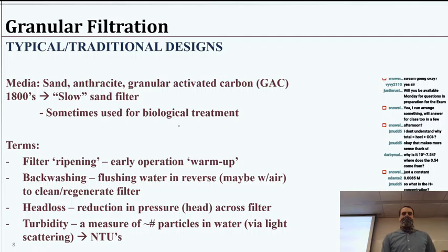The activated carbon, usually we're using that more for chemical type stuff. If we've got groundwater that's contaminated with petroleum products, we'll usually be pumping that up and out through a granular activated carbon filter. It will be granular filtration, but that's more of a chemical process rather than particle removal. So we're going to keep most of what we talk about here in regards to particle removal, although the same type of technology is working with the activated carbon. You just would have to regenerate that a little bit differently.